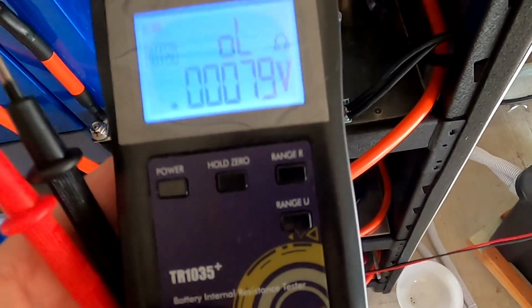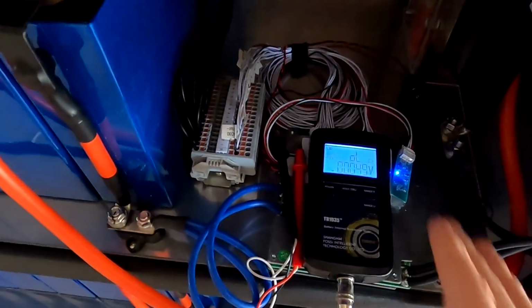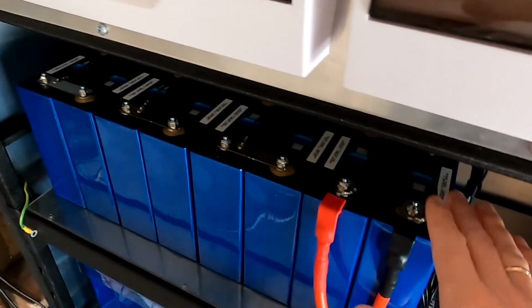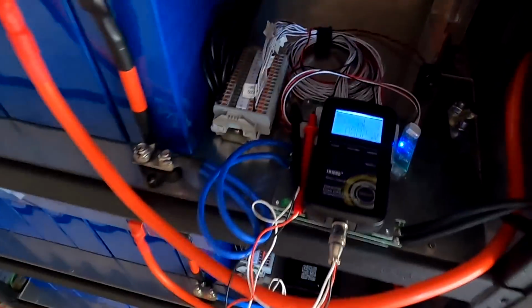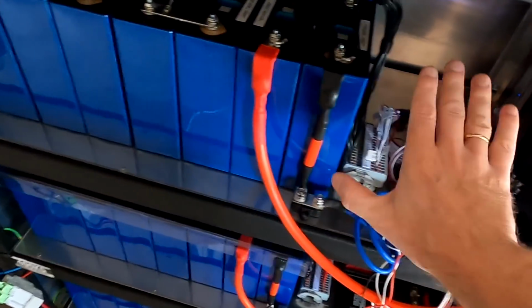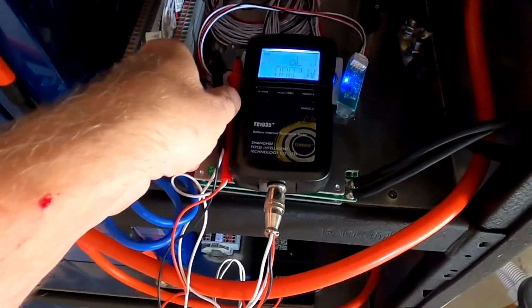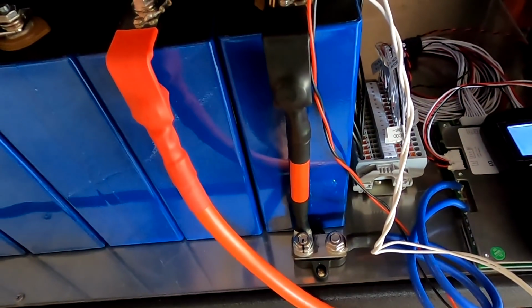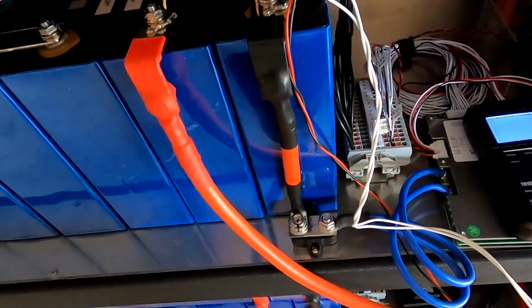I've got my battery internal resistance tester here. Before we fully charge, I want to measure the internal resistance of the whole battery bank as such. For this purpose, we turn off our top battery bank here with a circuit breaker, so this battery is completely isolated from the rest of the system. I'm going to measure here on top of the bus bar next to the terminals.